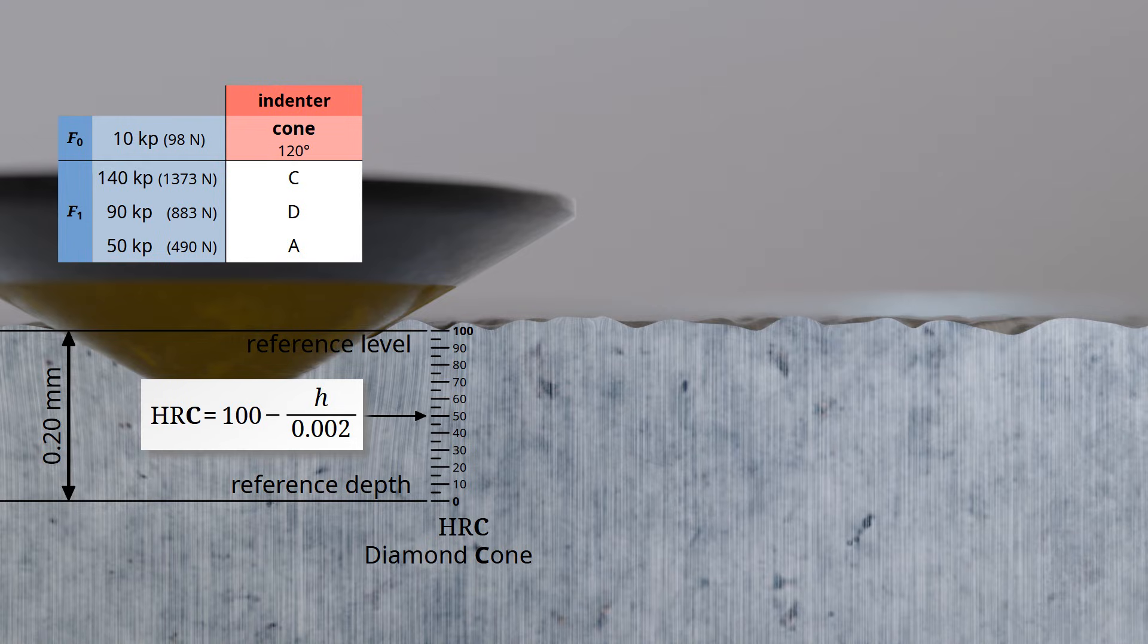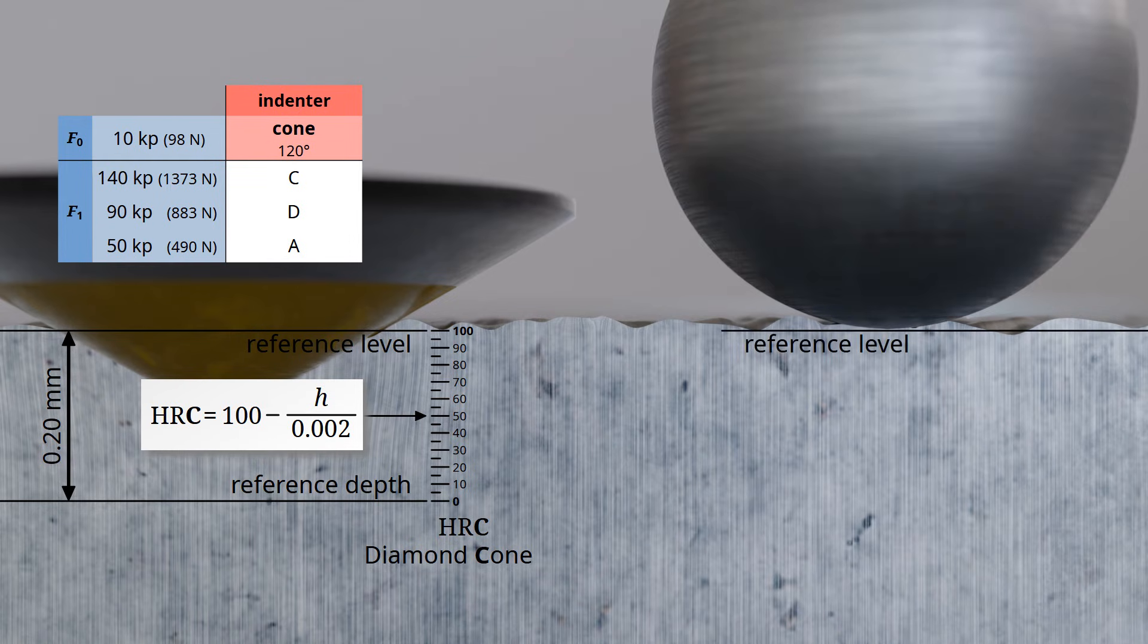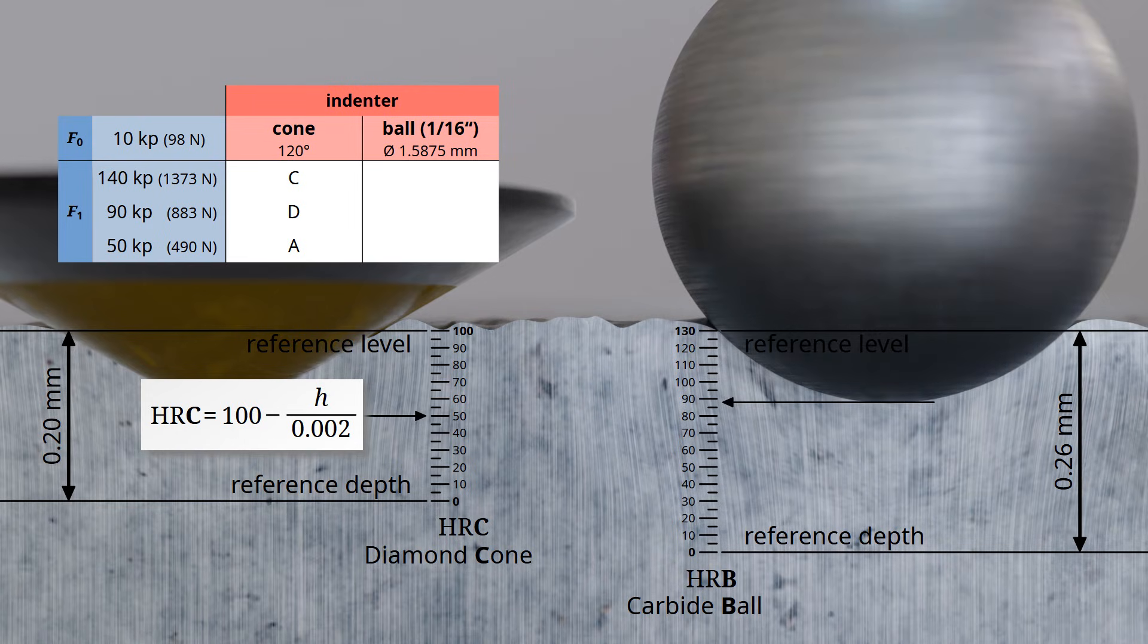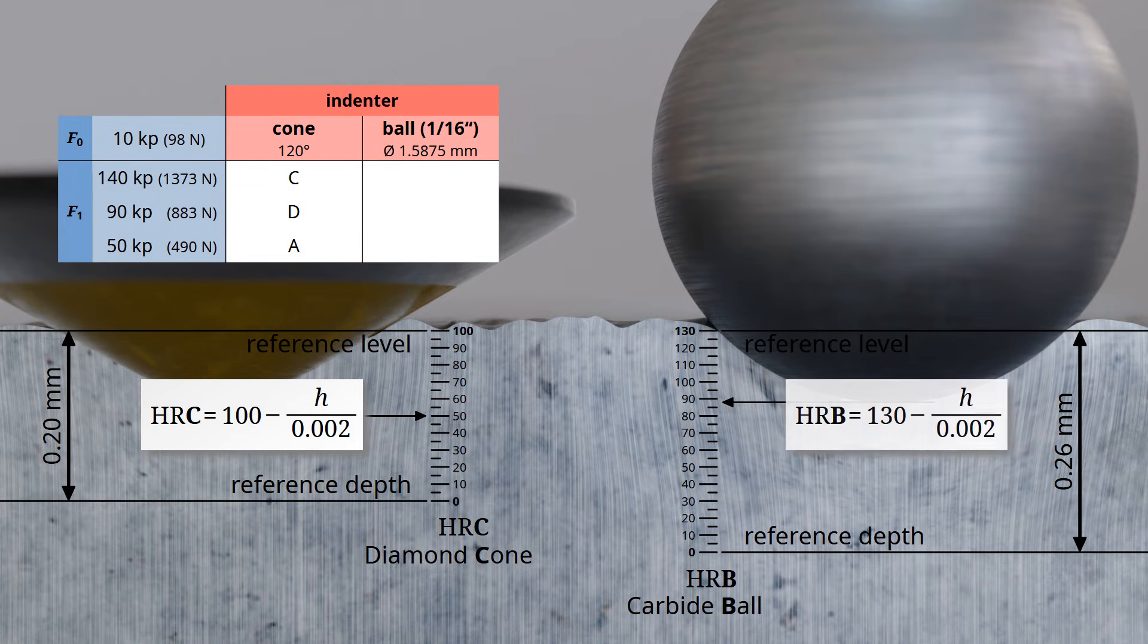When testing relatively soft materials, a diamond cone would penetrate too deeply, resulting in an indentation that exceeds the reference depth of 0.2 mm. For this reason, soft surfaces are tested using cemented carbide balls, and the reference depth is extended to 0.26 mm. The cemented carbide ball has a diameter of 1/16th of an inch, which equals 1.5875 mm. The hardness values are still subdivided in increments of 2 micrometers. Therefore, the use of cemented carbide balls results in hardness values ranging theoretically from 0 up to a maximum of 130. Using the given formula, the Rockwell hardness value HRB can be calculated based on the indentation depth h, with the depth specified in millimeters.